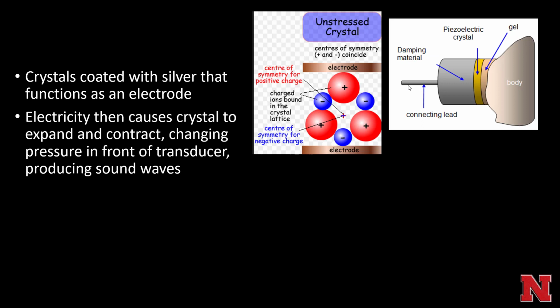These piezoelectric crystals are coated with silver that functions as an electrode. That electricity causes the crystal to expand and contract, creating a pressure front in front of the transducer, which leads to the sonographic wave going into the patient.